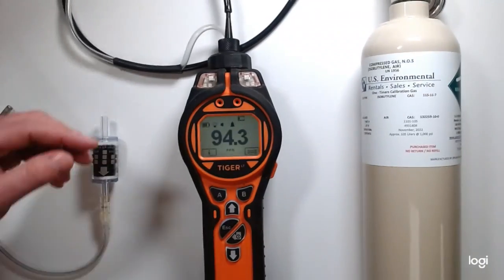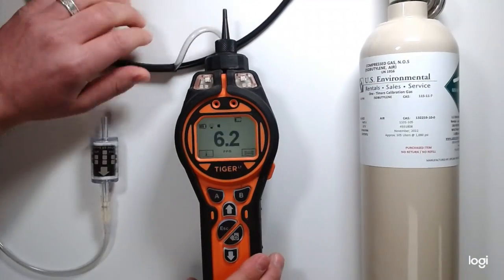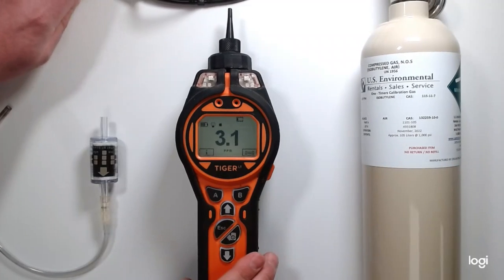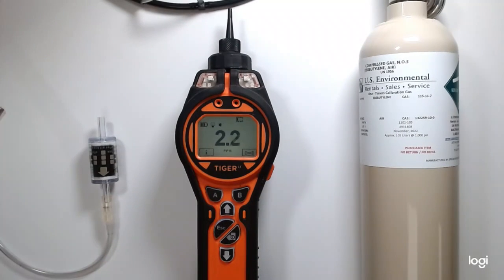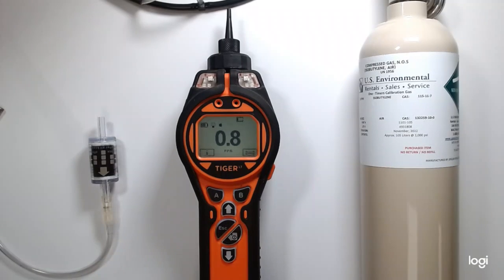We can now turn off our gas, remove the hose, and this is where we would do a humidity check. Most stations have a humidity tester. You just hook it to the hose and let it run for a few seconds to make sure you don't have a spike in readings. And this is a basic calibration of an Ion Science Tiger PID.